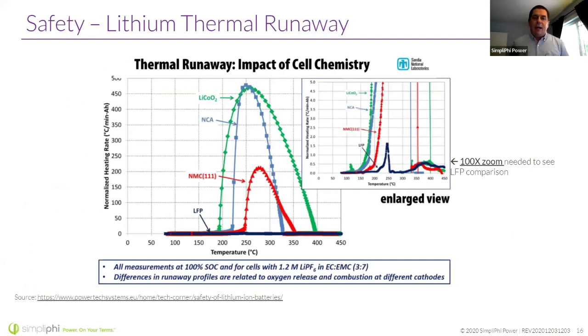On this graph, we're going to identify what happens to these various battery chemistries at various temperatures and the energy that's released. As we move on the horizontal axis from left to right, we are increasing temperature. You can see the green graph picks up first, it's the earliest temperature to start its thermal runaway or energy release event. The red line is the NMC battery we've been talking about as fire prone, used in electric vehicles often, and some home batteries as well. Our LFP line is there, but on the large graph you can't really see it. We actually have to zoom in 100 times to see the lithium iron phosphate curve. So again, it starts later, at a higher temperature, and it doesn't release as much energy before essentially collapsing back down to a non-energy released state.